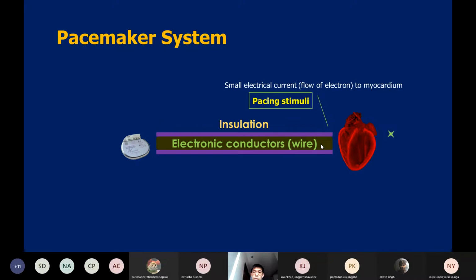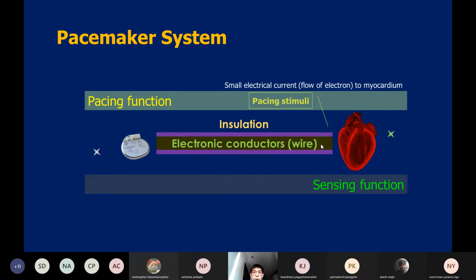And when you pace the patient, the pulse generator usually delivers a small electrical current through this lead to the myocardium. This is called the pacing stimuli. The device can also have a sensing function. The lead receives the electrical signal from the heart and sends it back to the pulse generator to analyze the intrinsic electrical activity of the heart. So this lead can generate electrical output and can also receive electrical signals from the heart. The generation of the electrical output is called the pacing function, and the receiving of the intrinsic signal is called the sensing function.